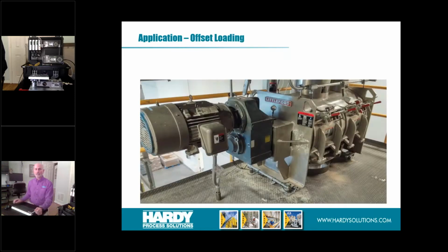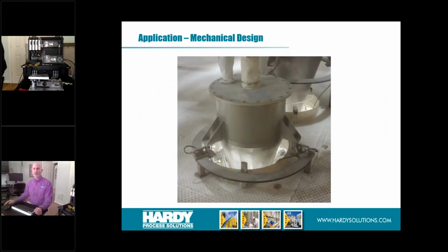A couple quick applications. This one has load cells at the bottom of the pump. The problem with this application is you've got a lot of weight on these load cells that's not centered, so you need to size all your load cells the same, but this offset shifts the center of gravity. You have to consider how much weight is on these cells plus the weight inside the pump, since what we're really trying to find is how much product is inside the pump when it's in operation. This is a good example of why a consultation with an expert is a good idea.